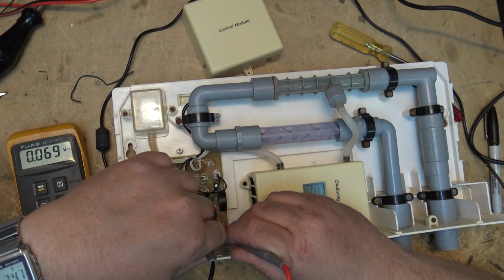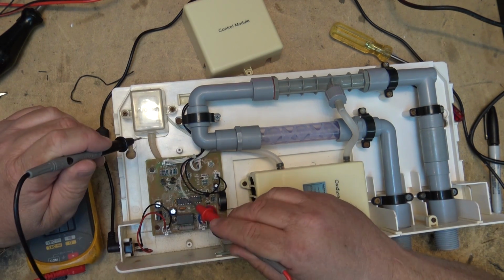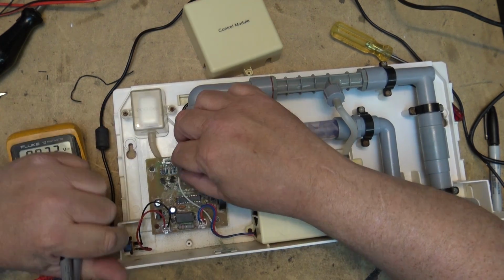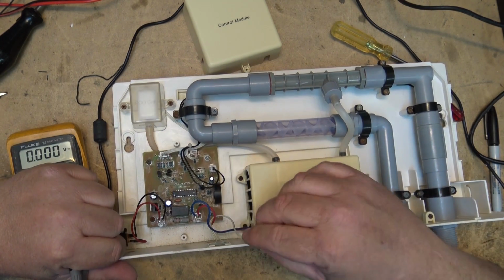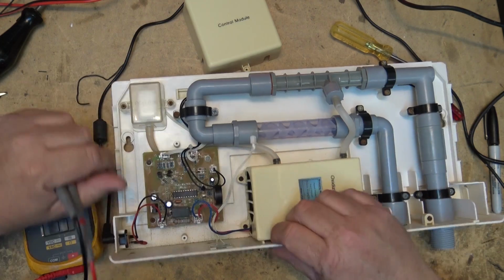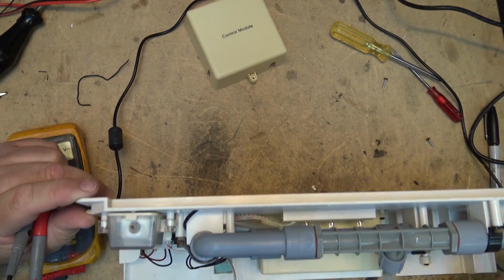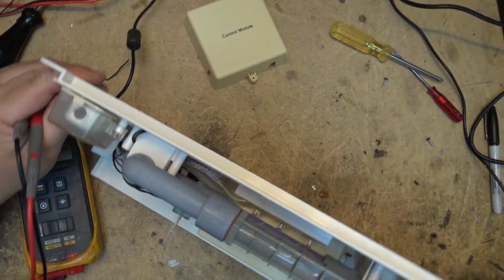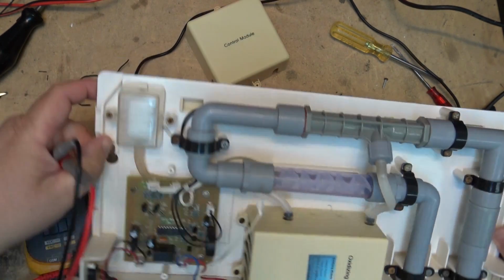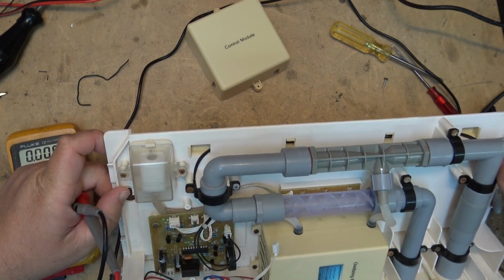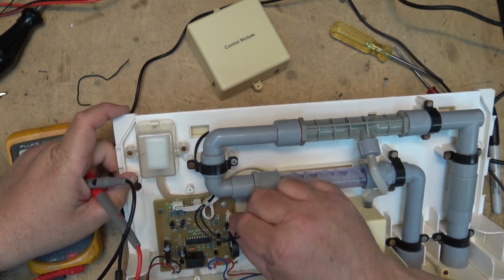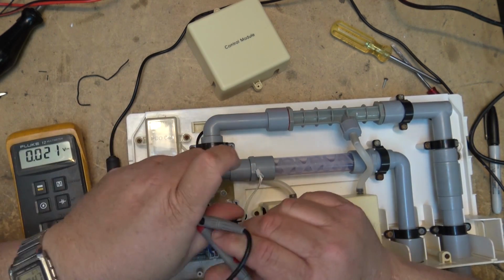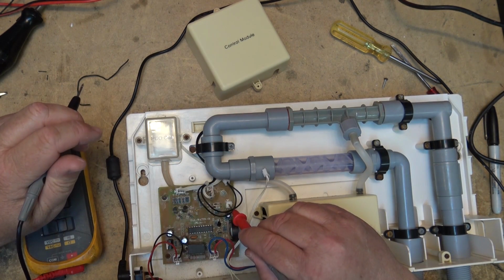Do we have power going out of the module? We have nothing coming out of this module, so this module is shutting it down. I'm curious as to why. There's probably a flow sensor in here that detects when water is flowing. I'm imagining it's this one over here, this black lead is the flow sensor. So let's just see if I short these together.